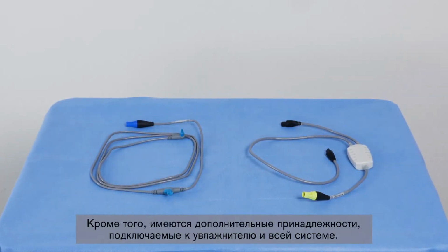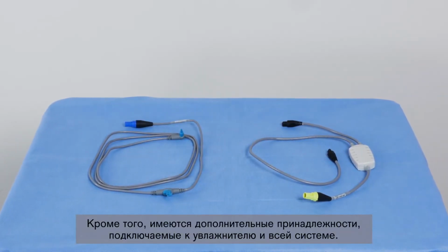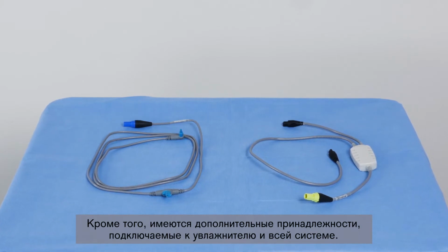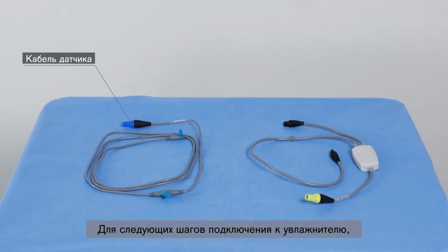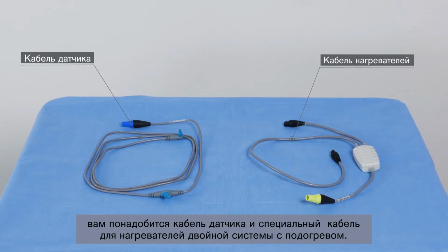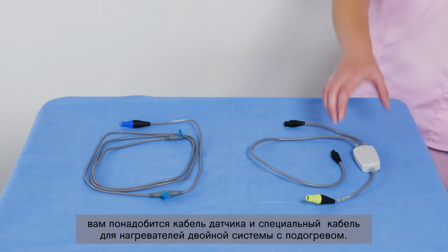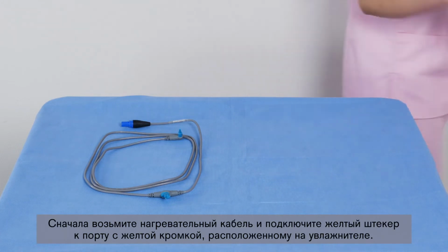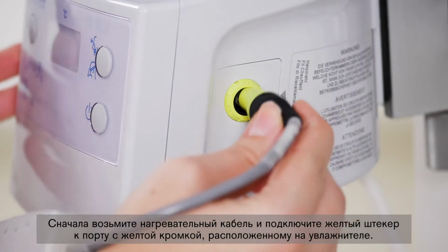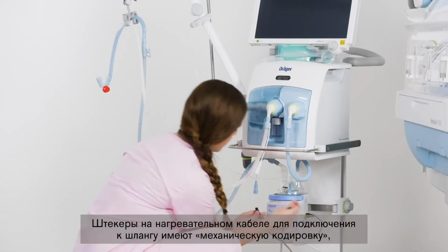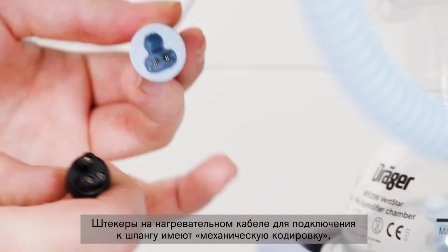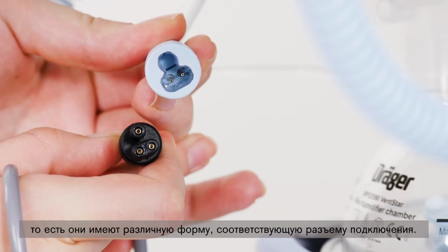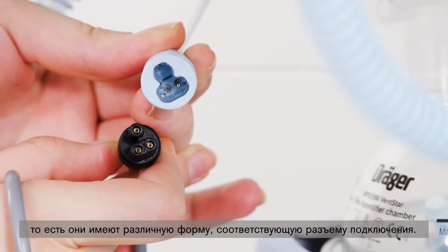In addition, there are further accessories to be connected to the humidifier and the entire system. For the next steps in the setup of connecting to the humidifier, you will need the sensor cable and the special heating cable designed for dual heated systems. First, take the heating cable and connect the yellow plug to the yellow-edged port on the humidifier. The plugs on the heating cable for connection to the hose are mechanically coded, i.e. they have a distinct shape that fits into the connection port.